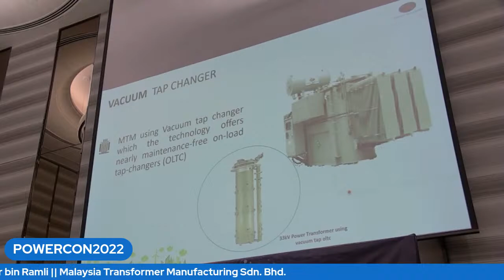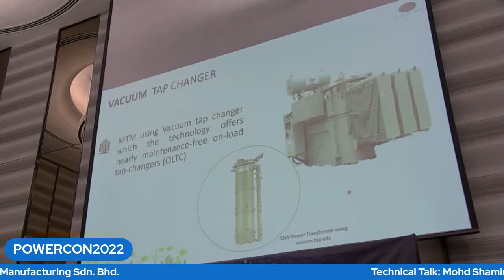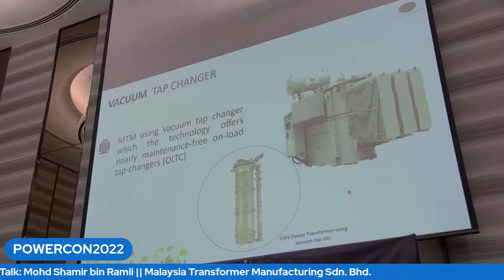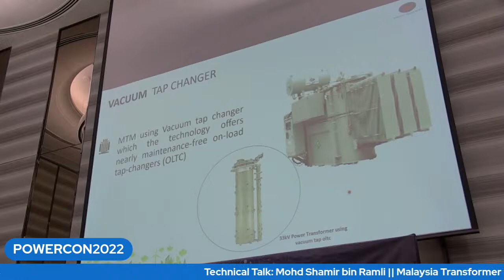In terms of reducing the carbon produced during operating the transformer, with a vacuum tap changer: normally, on the old tap changer technology, we have arcing inside the diverter switch every time they change the tap, so that produces carbon. But with this technology from MR or other OLTC providers, they use a vacuum tap changer, in the sense that the arcing or the switching is done in a vacuum chamber, a vacuum flask. Hence, there will be no oil arcing inside. So the maintenance interval will be longer. You don't have to maintain the oil as often.